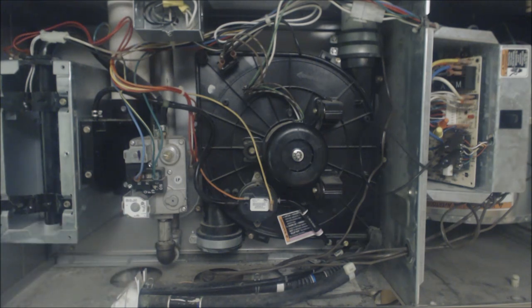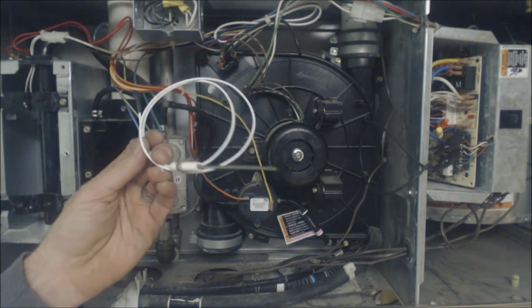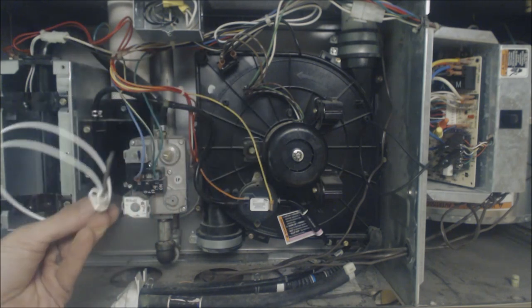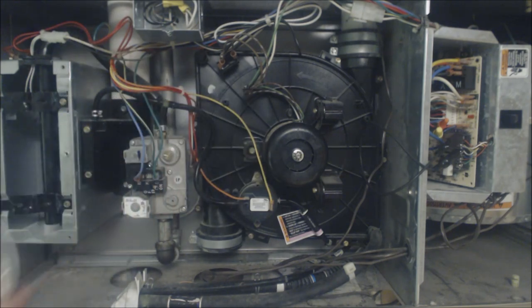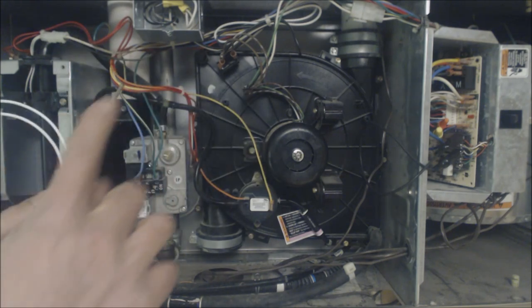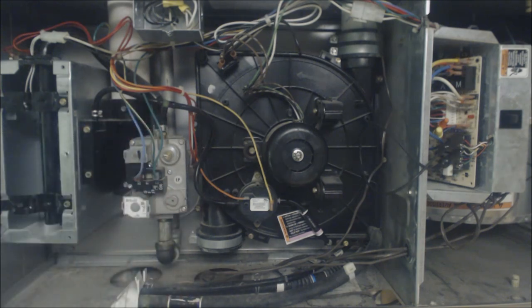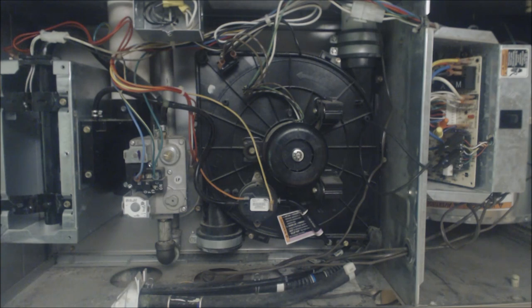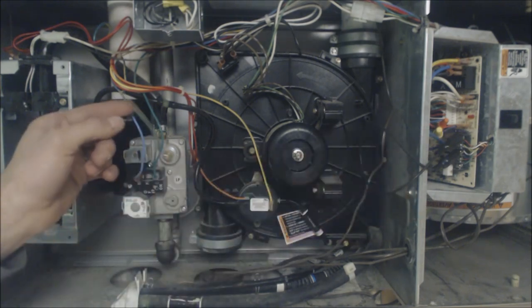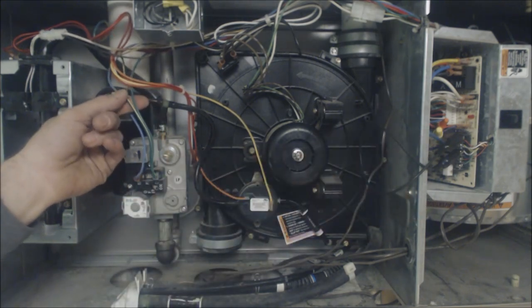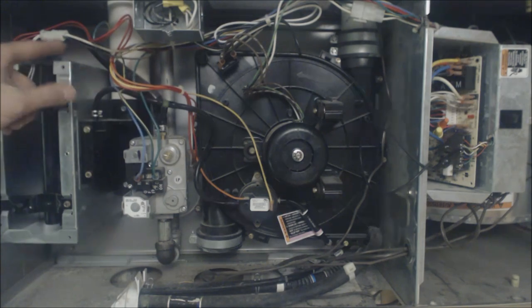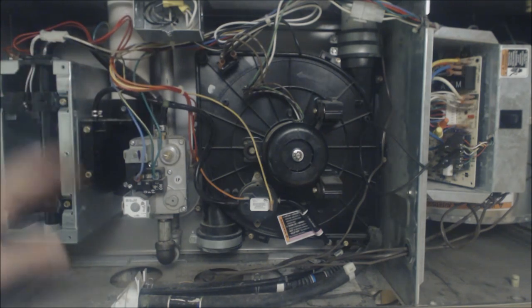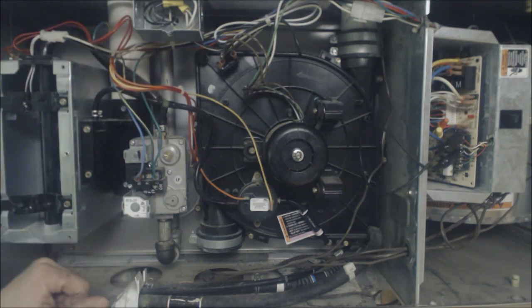That looks like this, okay, it's a flame rod that's immersed in the flame. This rod right here is immersed in the flame and the control board is actually looking for a DC micro amp reading back at the control board via the ground wire that's attached to the frame.